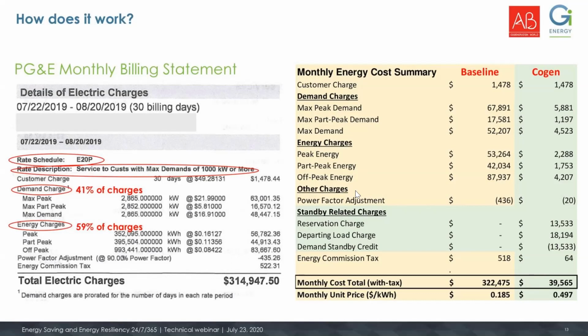That's something we can take care of. We usually ask the customer to look at their electricity and thermal bills, and we need to understand their electrical and thermal infrastructure, central utility plants, etc. Then we take the data and simulate the operation of a cogen unit, understanding how much will remain to be supplied by the utility when the cogen unit is in operation. A cogen unit shouldn't be sized on your peak load if you're going to stay grid parallel, and staying grid parallel is usually the first approach to these projects. So we size on an optimum balance between peak load and base load, maximizing hours of operation and extracting maximum value from the asset.